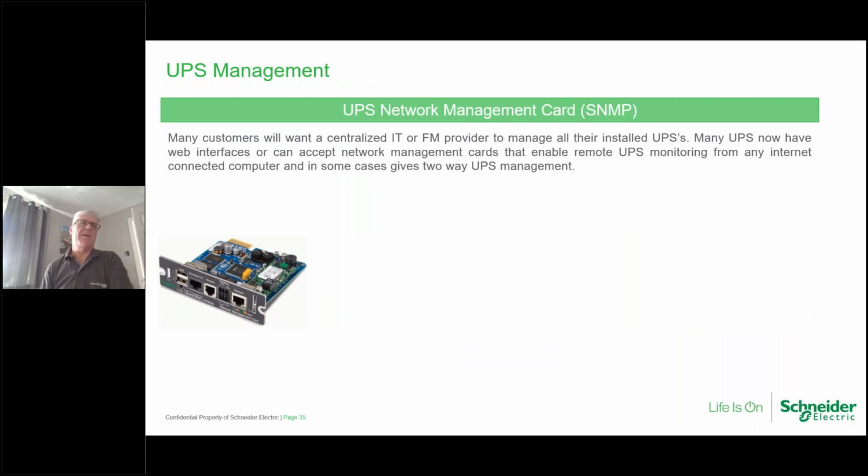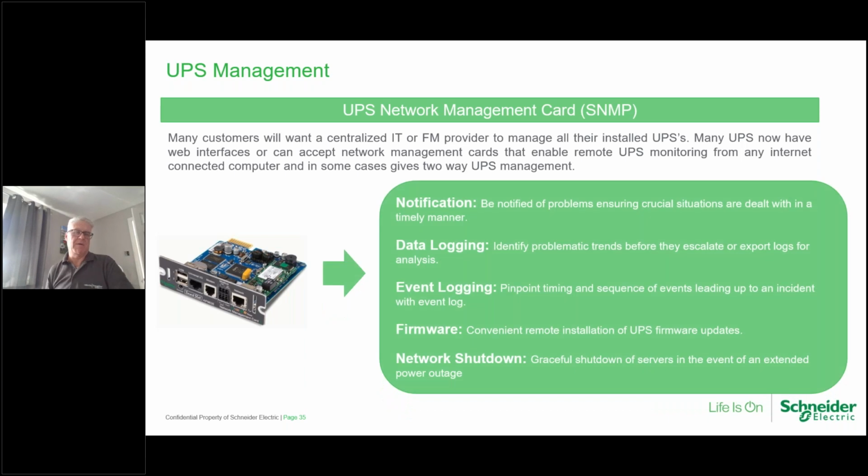We can put in a number of cards in there to report out on whatever we want to do. So is it SNMP reporting, or is it Modbus technology because we're reporting back to a building management system? Either way, whether it's through our NOC or through individual pipeline into our UPS, we can understand what it's doing.